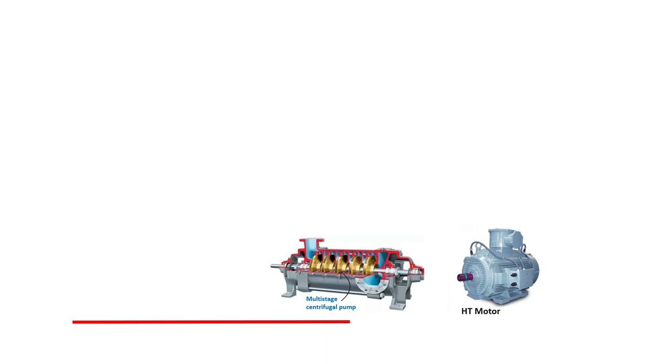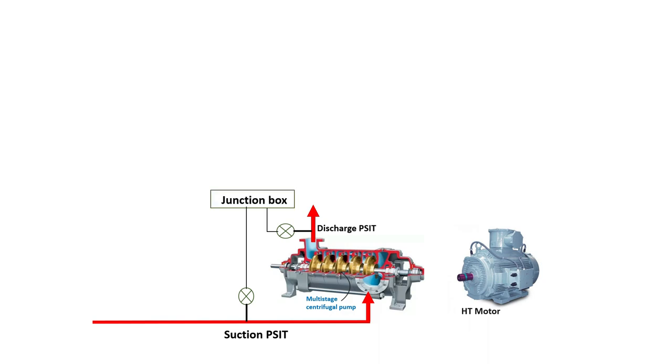Since it is a complex control signals scenario for a pump and motor, we have considered a multi-stage centrifugal pump and an HT motor so that the complex control signals can be discussed with different control systems. The multi-stage centrifugal pump has a suction line with a suction pressure transmitter, which is a safety transmitter, and a discharge line with a discharge pressure transmitter, also a safety transmitter. These run into a junction box, and we have DCS panels and PLC panels — two different panels.